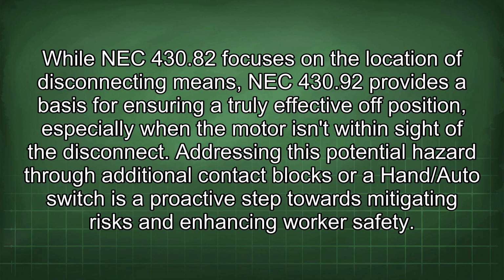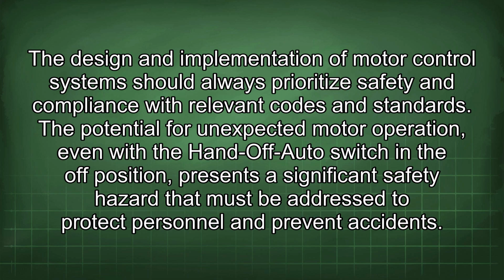Addressing this potential hazard through additional contact blocks or a hand/auto switch is a proactive step towards mitigating risks and enhancing worker safety. The design and implementation of motor control systems should always prioritize safety and compliance with relevant codes and standards. The potential for unexpected motor operation, even with the hand-off-auto switch in the off position, presents a significant safety hazard that must be addressed to protect personnel and prevent accidents.